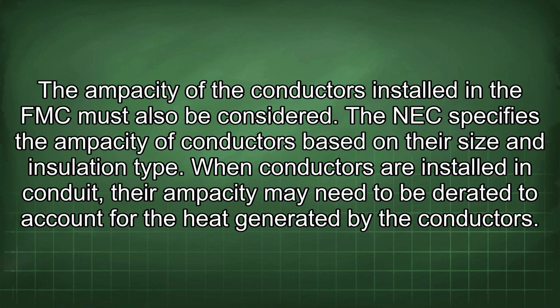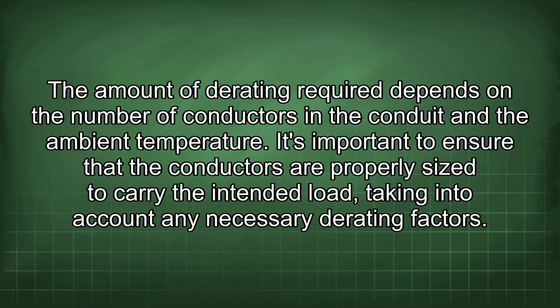The ampacity of the conductors installed in the FMC must also be considered. The NEC specifies the ampacity of conductors based on their size and insulation type. When conductors are installed in conduit, their ampacity may need to be derated to account for the heat generated by the conductors. The amount of derating required depends on the number of conductors in the conduit and the ambient temperature.